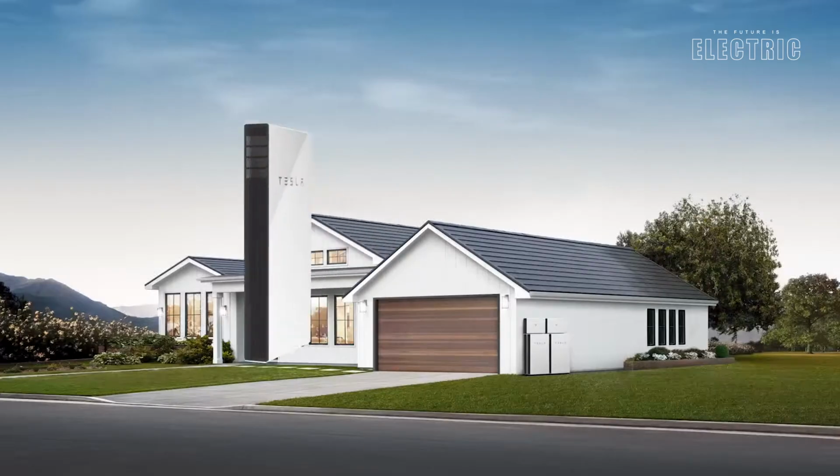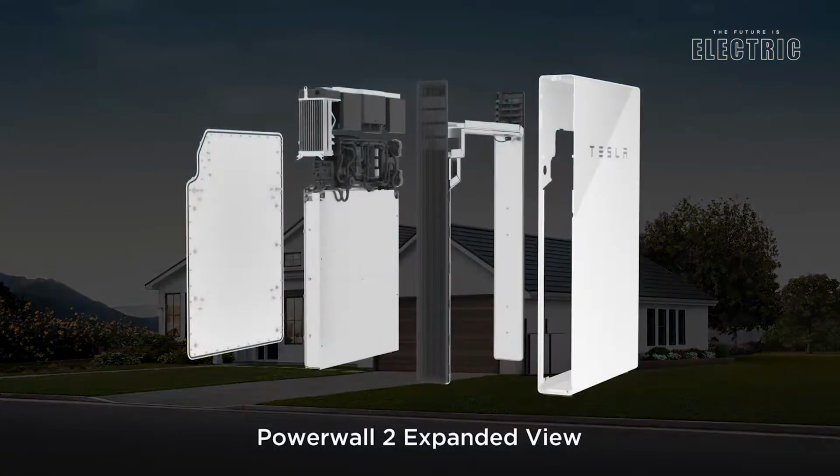All right, so why the Tesla Powerwall 2? There are other options available in the market. So let's understand what we have back there. So the bottom 2/3 of that compartment is dedicated to the battery cells themselves, similar to the one I'm holding here. There's around 5,400 of these making up the battery pack, which is 13.5 kilowatt hours.